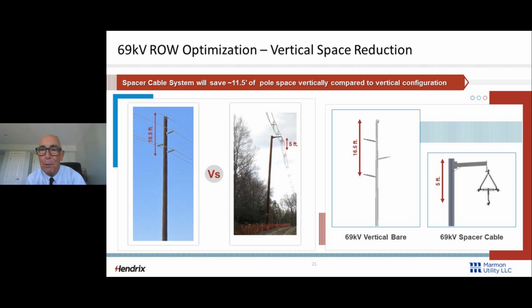Okay, so how are we optimizing our right of way? What do we really want to do? Let's go through this piece by piece. We basically want to reduce the profile of the whole transmission line. If you look on the top left, you'll see a bare wire 69 kV that is constructed in a vertical construction. You can see from the top of the pole down to the lower phase, we've got about 16.5 feet. Right next to it, you have 69 kV spacer cable. And you can see from the top of the pole to the bottom of the bundle, that's 5 feet. So we're essentially saving 11.5 feet of vertical space.